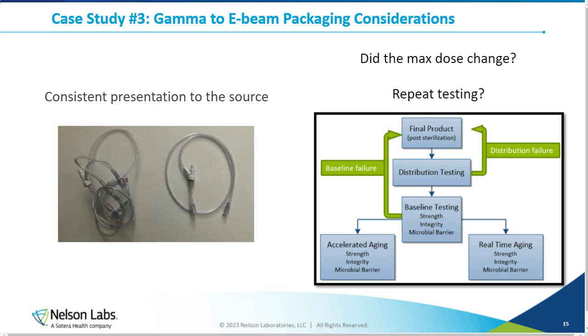The other thing is, even if your sterilization dose hasn't changed, your max dose may change because of that multiplier. You saw in Bryce's example that for gamma it was 25 to 40, whereas that could go up to 25 to 50 for E-beam. And anytime the max dose changes, you're going to have to do some testing to support that. Again, on this one you can probably get by with baseline up to baseline testing to show that a little bit higher sterilization dose is not going to negatively affect the packaging in such a way that it will develop sterile barrier breaches during use.